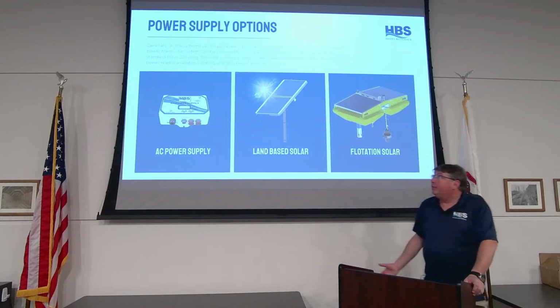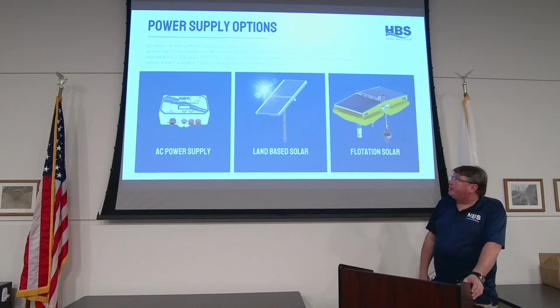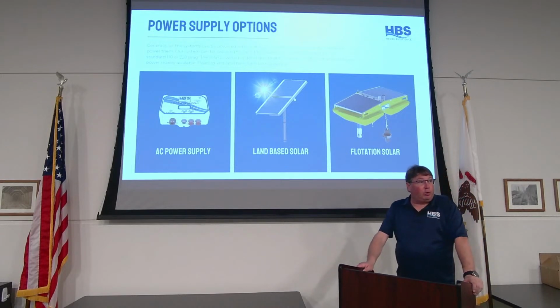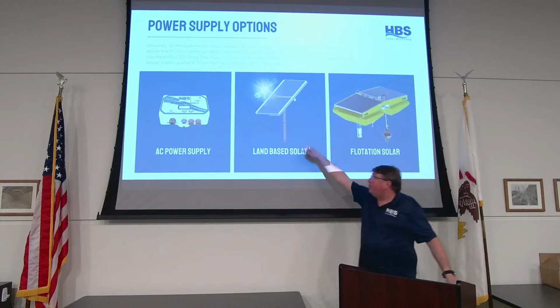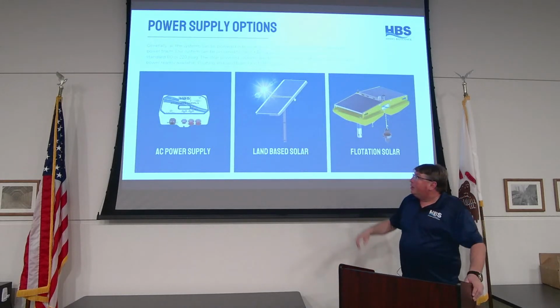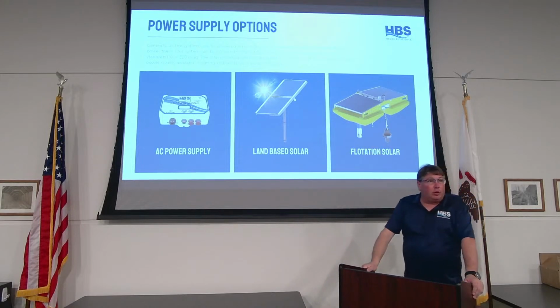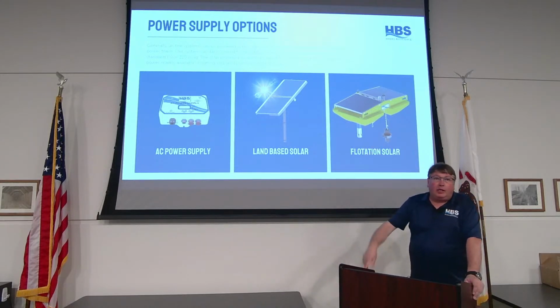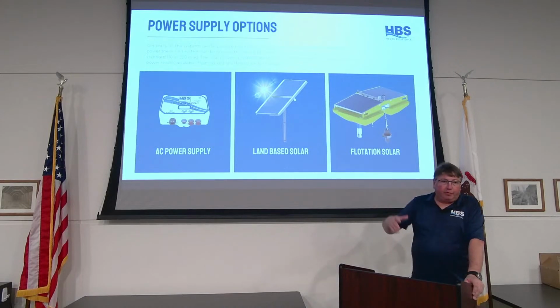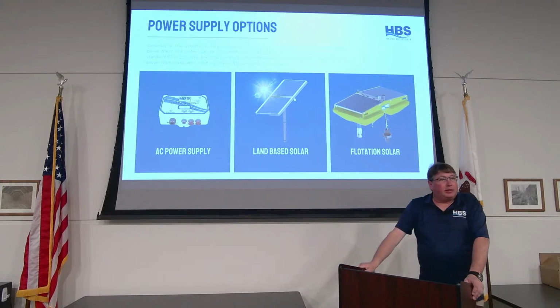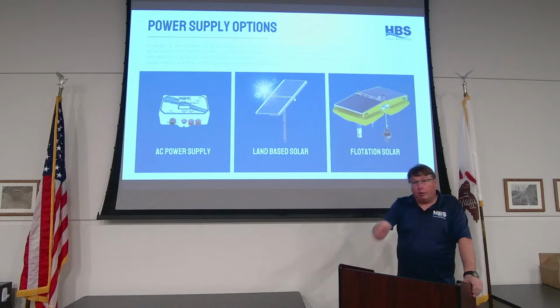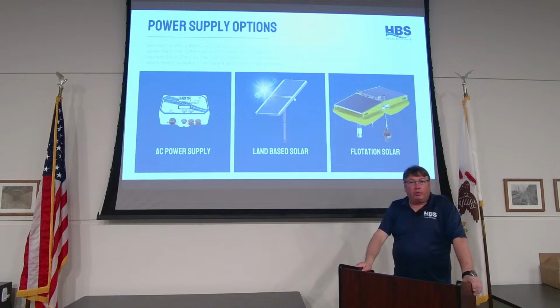You can have different types of power out there. So at one site, we've got to use solar power. We have a stand-up that just buries in the ground to about right there. You run the cords up, you plug into the back of the solar controller. It's got six batteries on it. You hook your transducer to your float, you hook a cable to it, you pull it out towards the middle, and you stake it off on the other side. So anytime you need to clean it, you just pull the steel cable on the other end, pull it to the bank, and wipe it off. That's kind of important with all ultrasounds: you have to keep the heads clean. You have to keep the transducers clean.